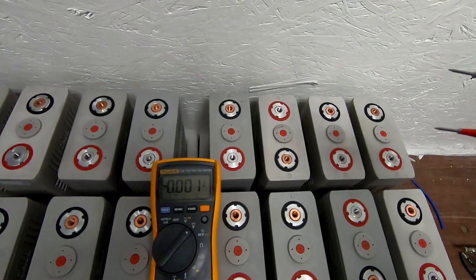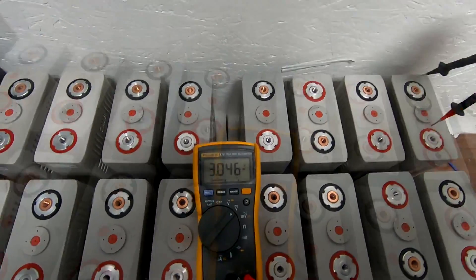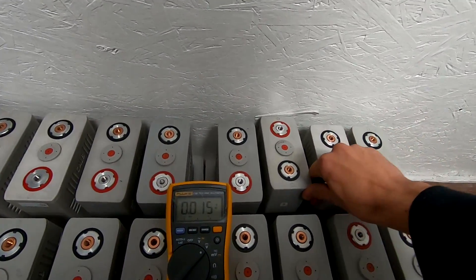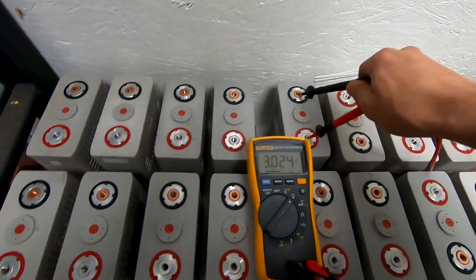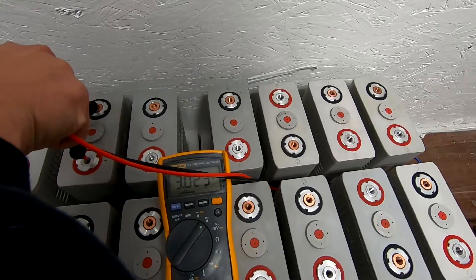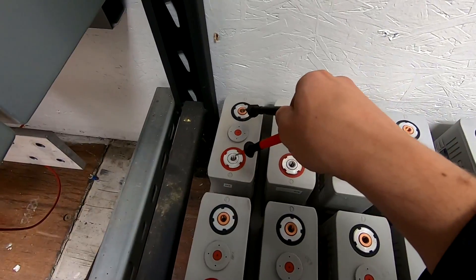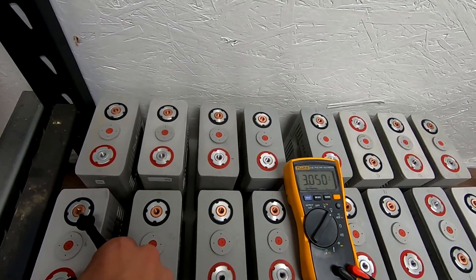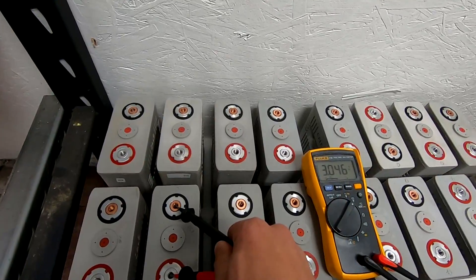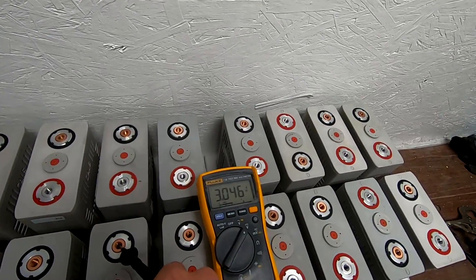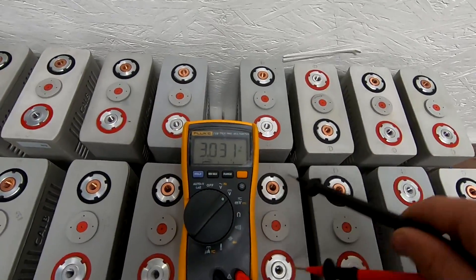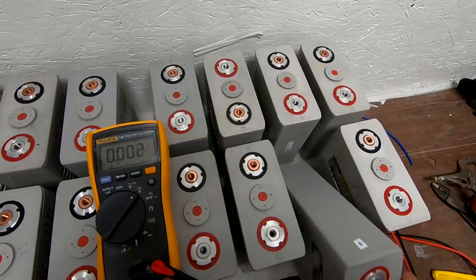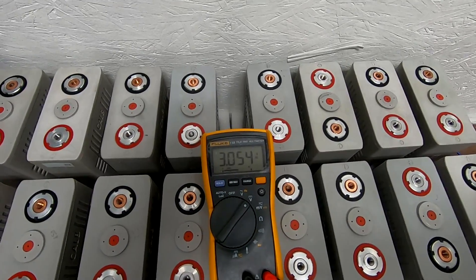So I'm going to go ahead and start reading cell voltages here. This is cell number 2 and I have 3.046. Cell number 5, 3.033. It looks like these have recovered a little bit. Cell 8, 3.025. Cell 9, I have 3.024. Cell 10, I have 3.025. Cell 11, I have 3.023. Cell 18, 3.035. Cell 19, 3.038. Cell 25, 3.050. Cell 26, 3.046. Cell 27, I have 3.0456 somewhere in there. Cell 28, I have 3.026. Cell 30, 3.031. Cell 31, 3.045. This is cell 32. Cell 32 is 3.049. Cell 33, 3.054.